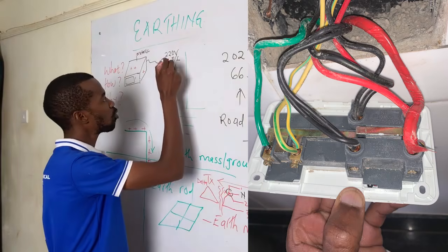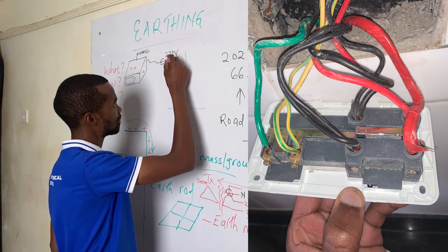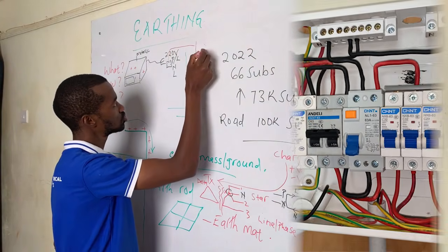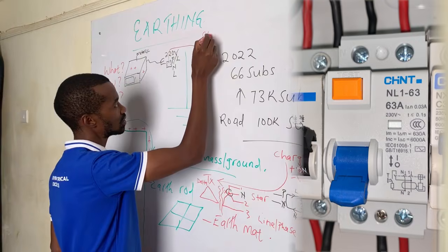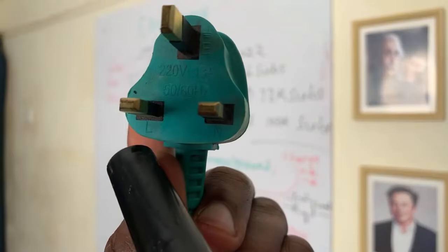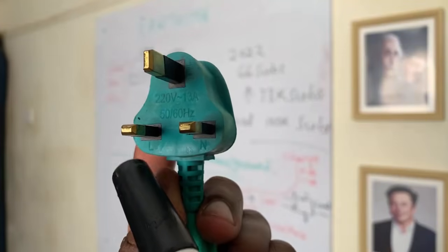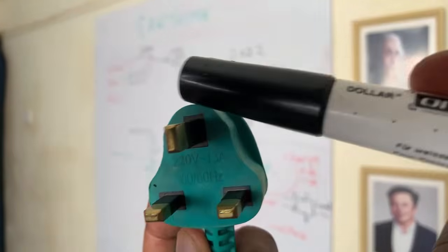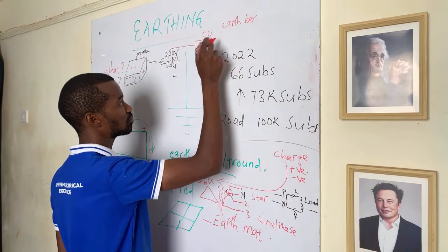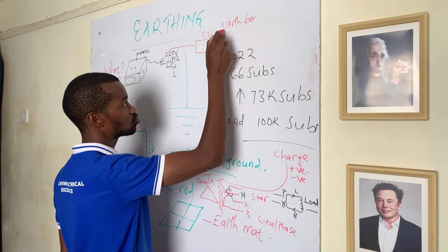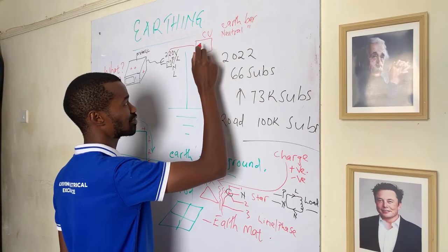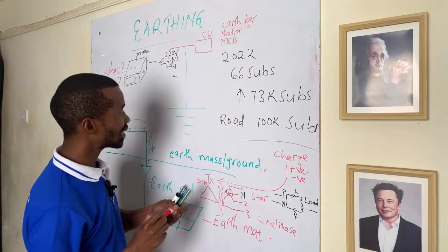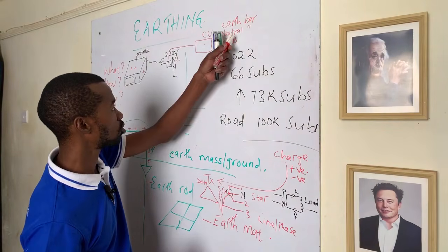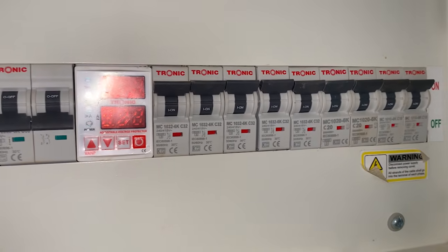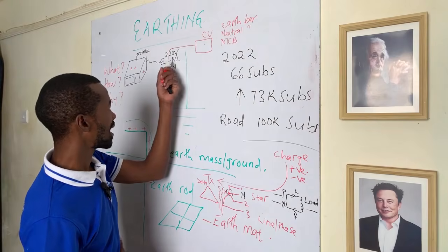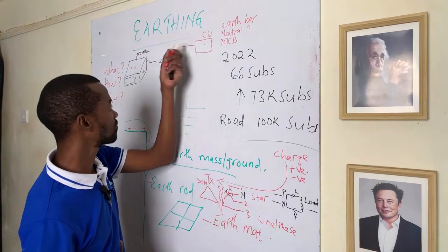The wall socket's earthing also has to go all the way to the consumer unit. Apart from our line and neutral going to the MCB, where many people put a lot of focus, we also have the consumer unit with the earth bar and the neutral bar. So as much as we connect the line and neutral to the MCB and the neutral bar respectively, the earthing has to be continuous all the way from the sockets.